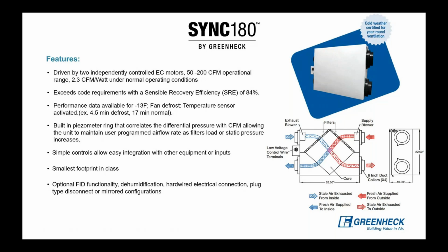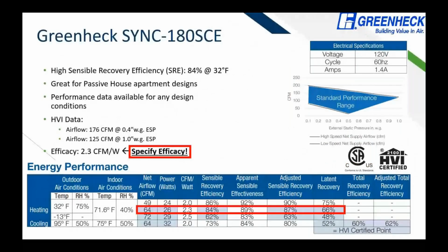So moving on, this Greenheck SYNC 180, like I said, it's got an 84% SRE at 32 degrees. It's really good for passive house apartment designs. This will shine brightly to the CPHC or the PHIUS certifier. This is something definitely worth designing around. But if you do, it's worth noting that you really should specify the efficacy on that drawing. The reason being is that this has a pretty high efficacy of 2.3 CFM per watt.